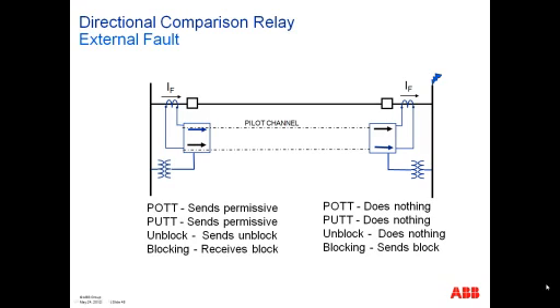Next. Then you have directional comparison relays, and these are used with either instantaneous ground overcurrent or impedance measurement. As the name implies, you're doing some type of comparison of fault direction, where the information from each end is transmitted to the remote end as to how it sees the fault. Is it forward at one terminal, or is it reverse at one terminal? And each terminal takes the information it receives and makes a decision whether to operate.